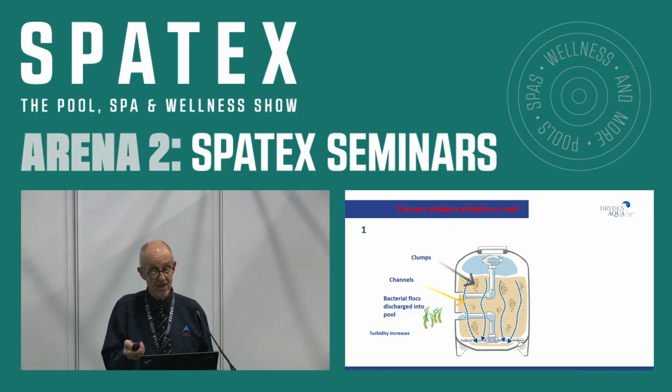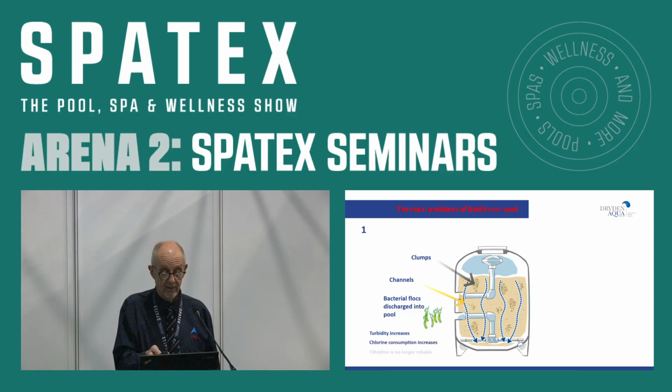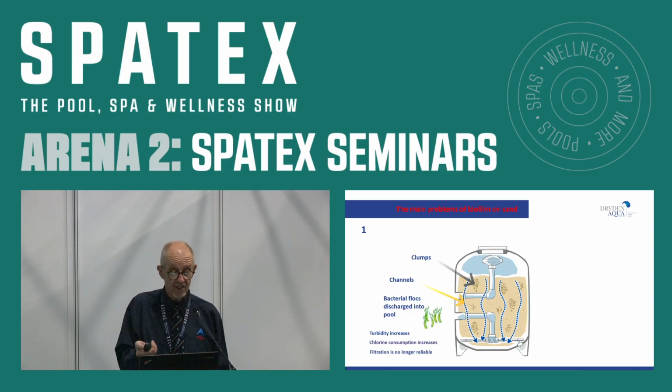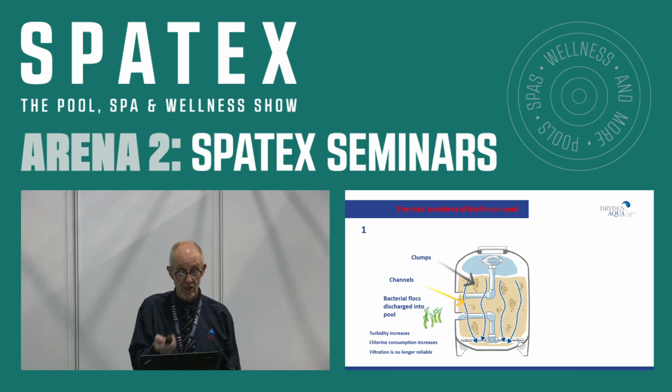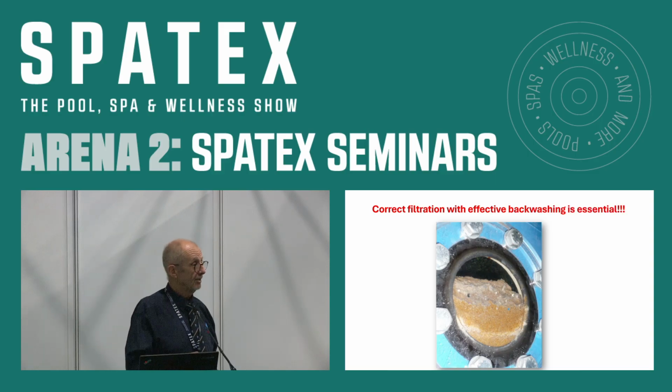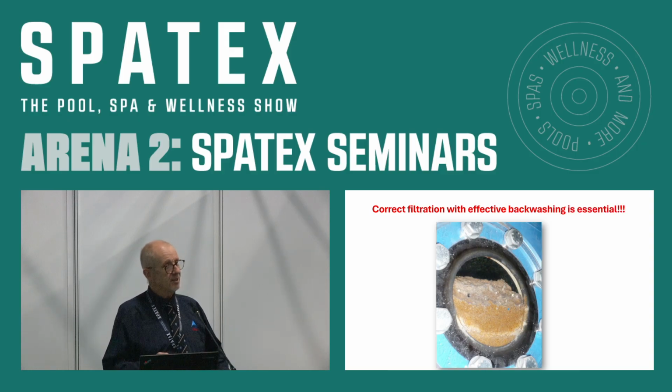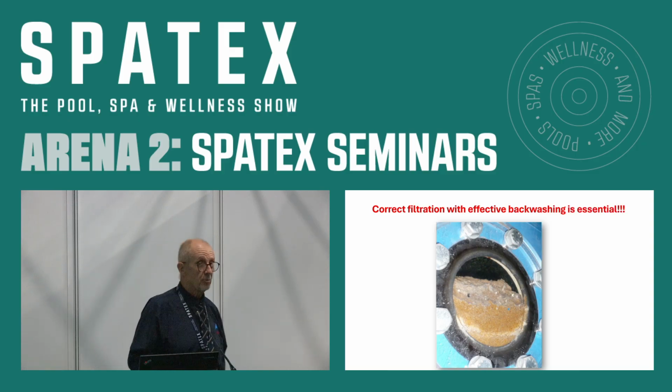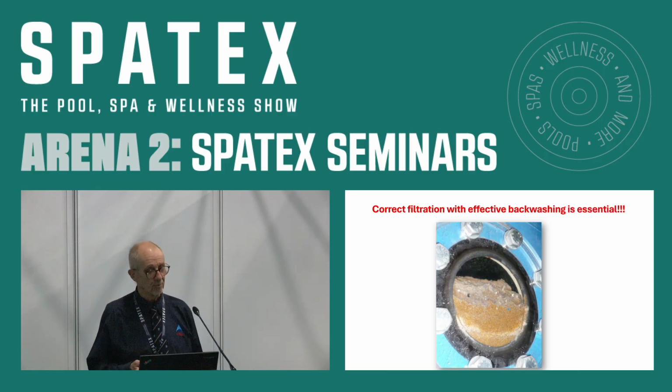Turbidity increases. Chlorine consumption increases. Like I've said, filtration is no longer viable or reliable. And this is the sort of thing that you see in the top of a filter. Now, what on earth is that? That's fatty deposits, oils, and underneath that, down to a pinch of you know what, it's a biofilm.